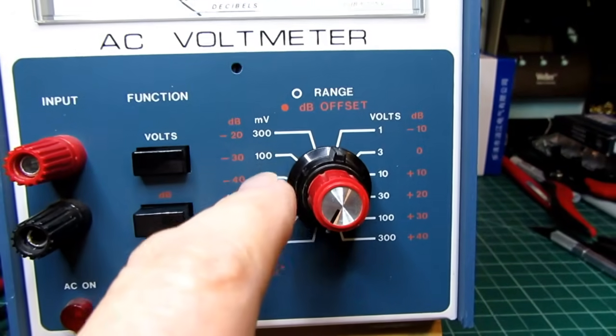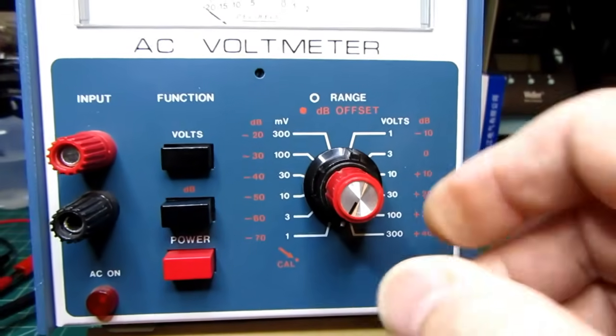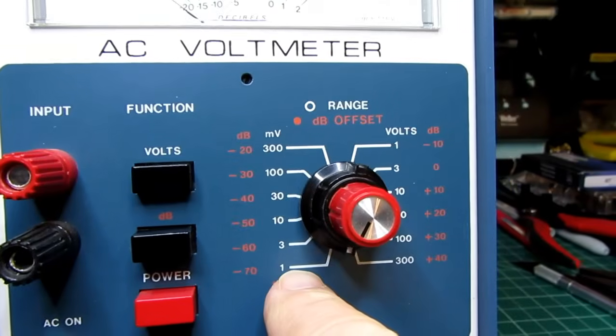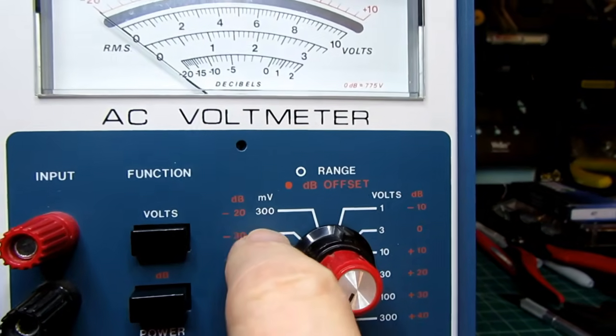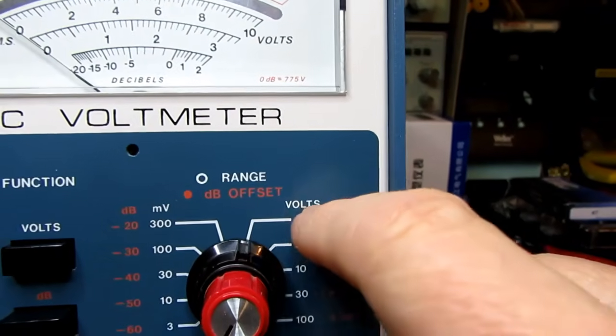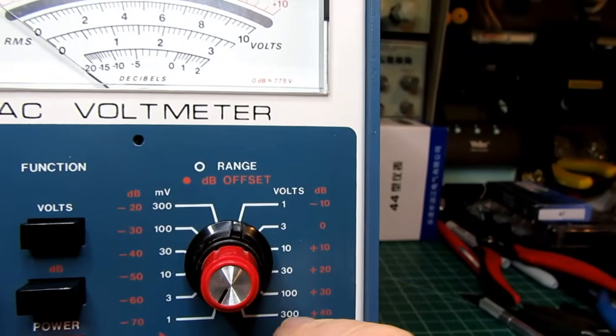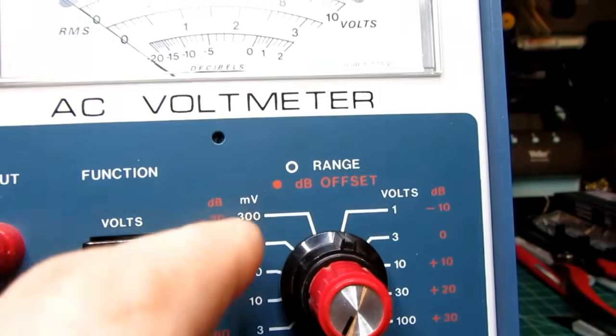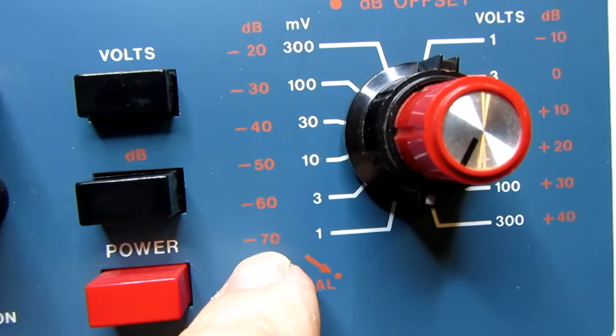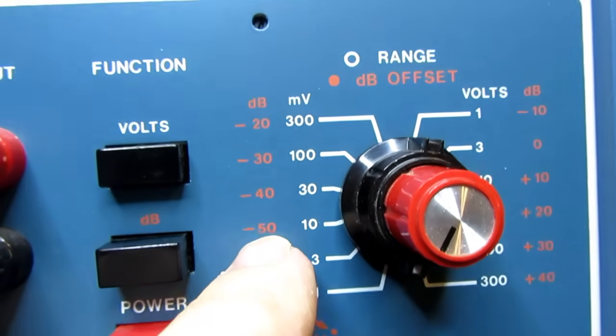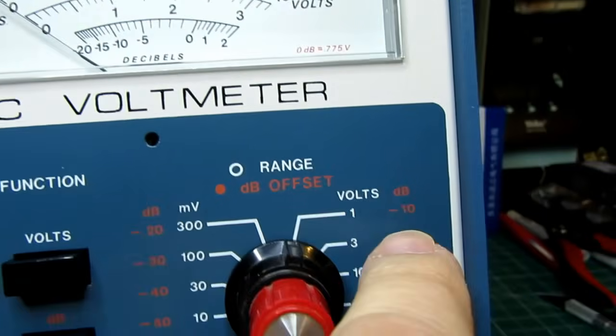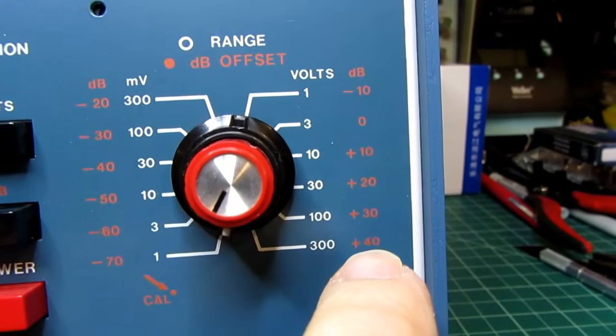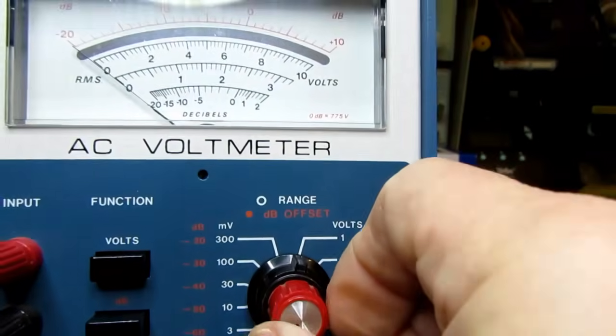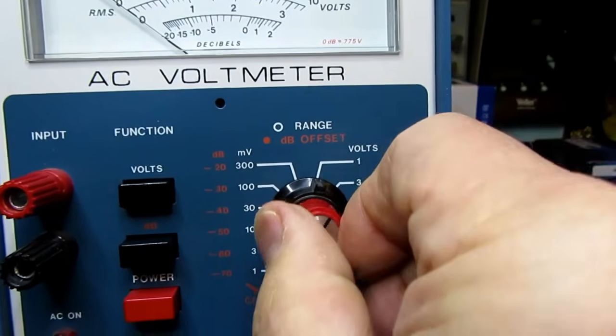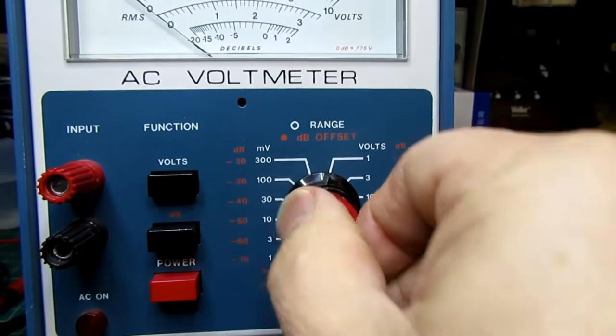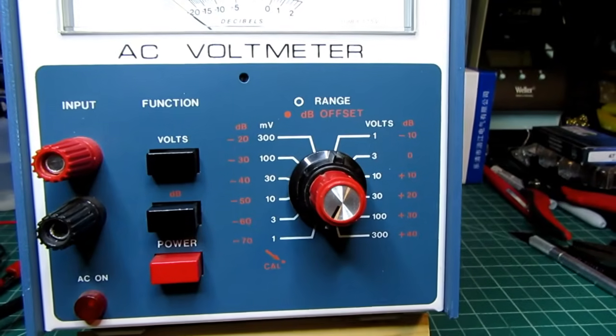There is a 12 position rotary range switch. It starts at the counterclockwise position with 1 millivolt full scale, 3 millivolts, 10, 30, 100, 300 millivolts, and then continuing with 1 volt, 3 volts, 10 volts, 30 volts, 100 volts, and 300 volts full scale. If we're in the decibel mode, it's -70, -60, -50, -40, -30, -20, -10, 0, +10, +20, +30, and +40. And there's also an offset adjust for the decibel mode, and that's this concentric red knob. If it's left in its full counterclockwise position, that's the calibrated position.